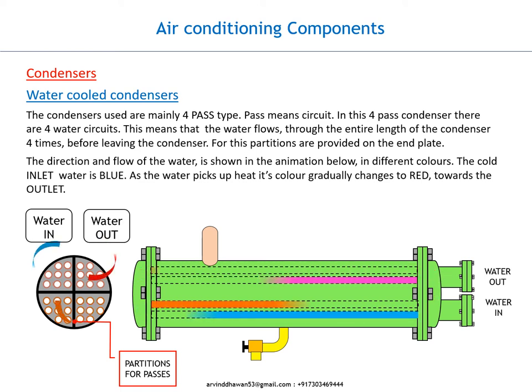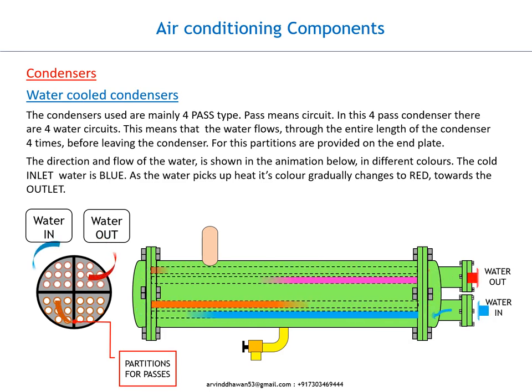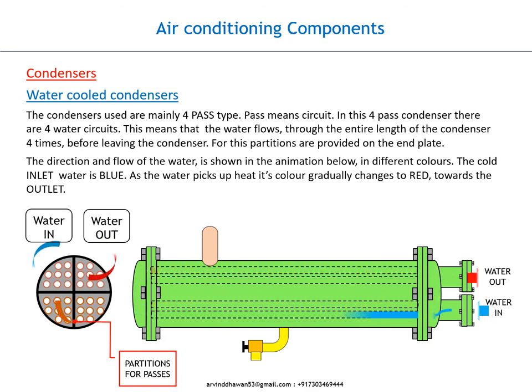The condensers used are mainly four pass type. Pass means circuit. In this four pass condenser there are four water circuits. This means that the water flows through the entire length of the condenser four times before leaving the condenser.